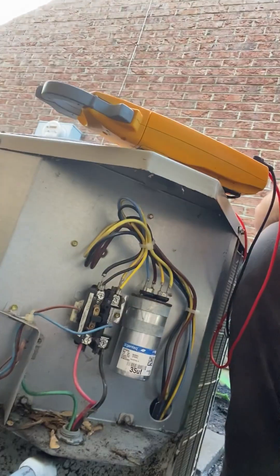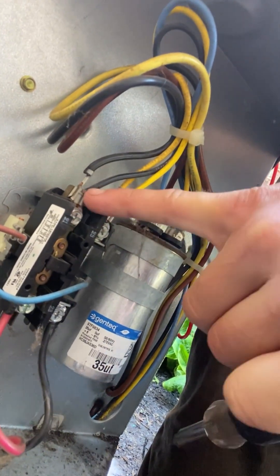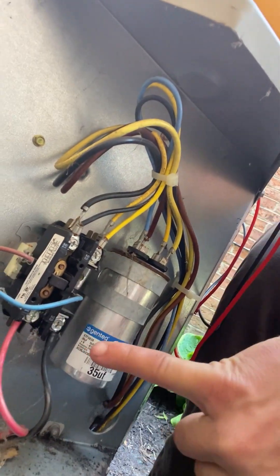One of the key things we do on all of our air conditioner checks — probably seems silly to some people and maybe they don't think it's a necessary part of the check — is we make sure all the screws here on this contactor are nice and tight. Now these come from the factory up here. Most of the time we're never going to find these loose, but we always want to check these too. These are what the installer has put together.